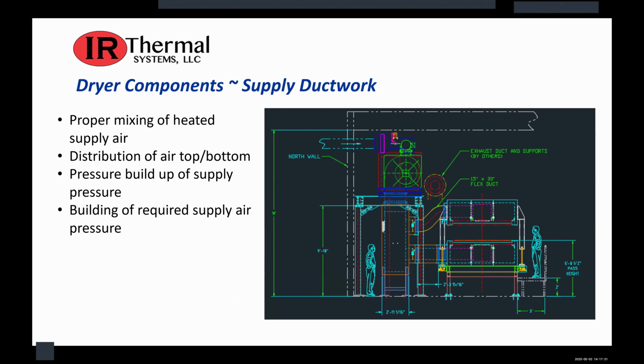The supply ductwork is often just looked at as a method of conveying air to the dryer, but it also serves a couple other purposes. It provides an area for the proper mixing of the heated air. Also, it distributes the air to the top and bottom of the dryer enclosure. It's hard to see, but there are small dampers prior to the supply to the top as well as the bottom. That helps you balance that air top to bottom. Also, every supply fan needs a specific amount of distance to build up the pressure required for delivering that air. So you typically have 2.5 times the diameter of the supply fan in distance within that ductwork prior to having any turns or splits.